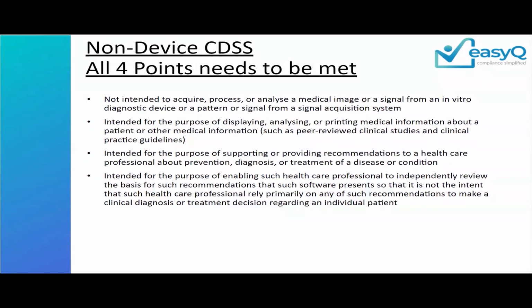Please, again, do not mix this up. CDSS is predominantly on the US FDA side. If you are a company in India or some other region, you still need to look into the regulatory requirements of those regions separately. This subject is in line with the overall SaMD discussion, and hence I thought to bring it up, just so that you are aware of what CDSS is and how we go about it. If we are a non-device CDSS, that is one case; if we are a device CDSS, it is nothing but what you follow for your medical devices. So you will be regulated. You need to go through either a 510(k) or a PMA based on your classification. The rest will follow from there.